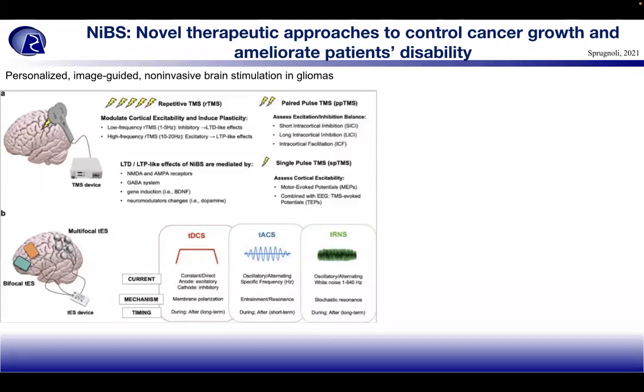Multifocal TES and bifocal TES on a TES device can deliver constant or direct current — anodal (excitatory) or cathodal (inhibitory) — or oscillatory alternating current at a specific frequency. For tRNS, the same oscillatory alternating current is applied at white noise from 1 to 640 Hz. Mechanisms include membrane polarization, entrainment, resonance, or stochastic resonance, and timing can be long-term or short-term.